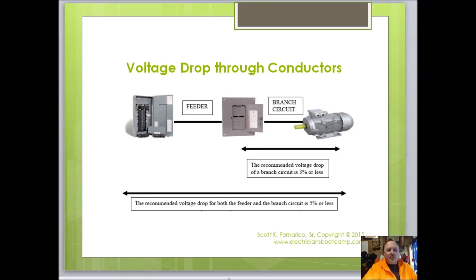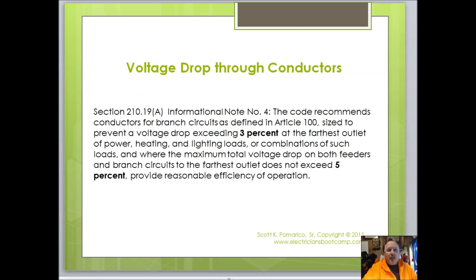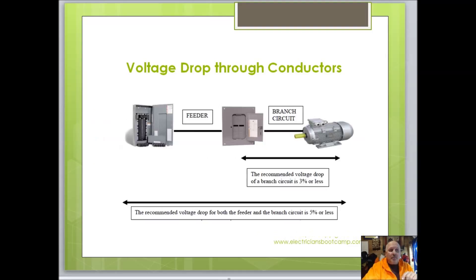When we talk about voltage drop, we talk about voltage drop through conductors. From the beginning where the service comes in to the last receptacle or motor, that would be five percent. For our calculations, we use three percent — from our panel or sub-panel to a particular device or motor. In the code, section 210.19(A) informational note tells us to use three percent, and five percent for both feeders and branch circuits. On the test, you'll be using three percent.